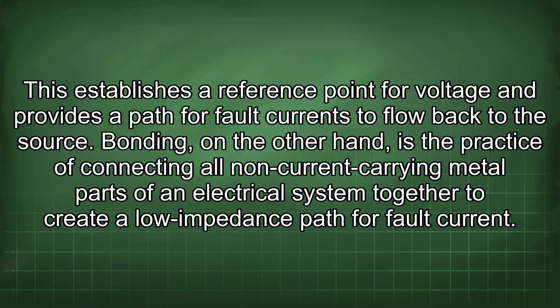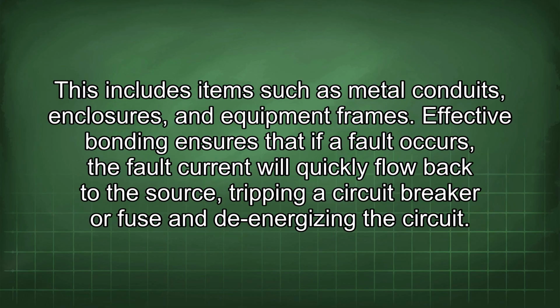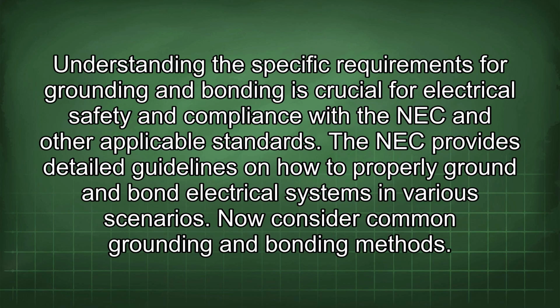Bonding, on the other hand, is the practice of connecting all non-current carrying metal parts of an electrical system together to create a low impedance path for fault current. This includes items such as metal conduits, enclosures, and equipment frames. Effective bonding ensures that if a fault occurs, the fault current will quickly flow back to the source, tripping a circuit breaker or fuse and de-energizing the circuit. Understanding the specific requirements for grounding and bonding is crucial for electrical safety and compliance with the NEC and other applicable standards. The NEC provides detailed guidelines on how to properly ground and bond electrical systems in various scenarios.